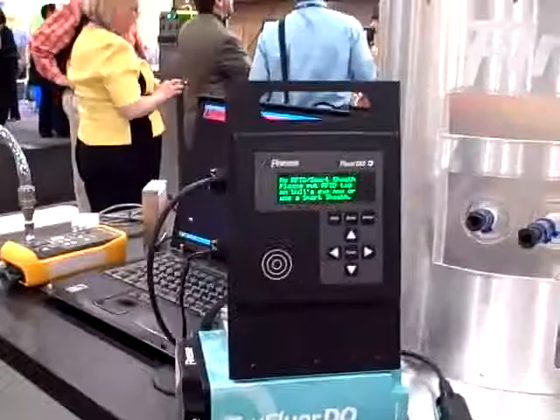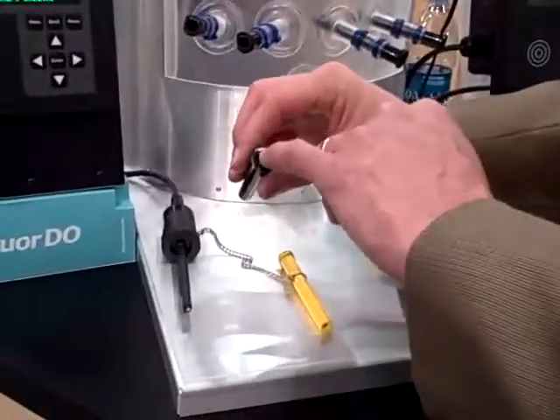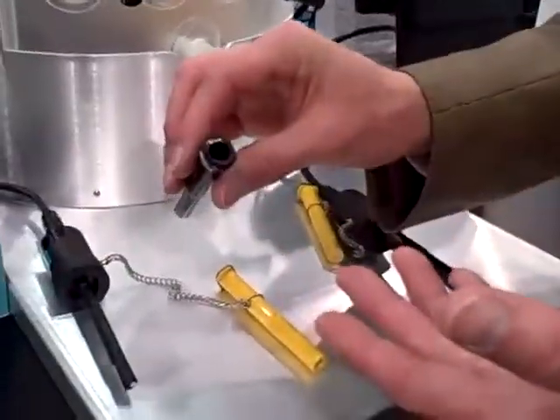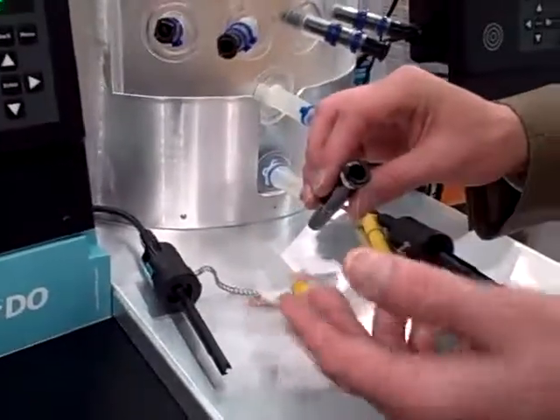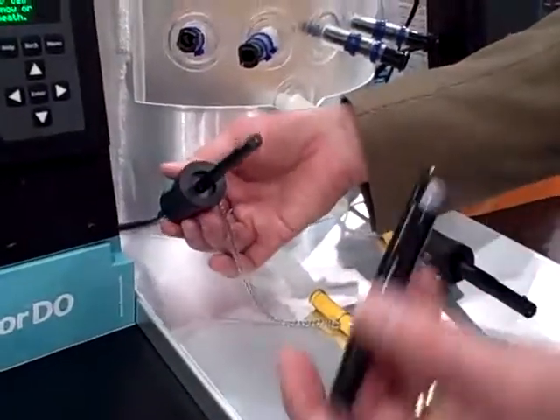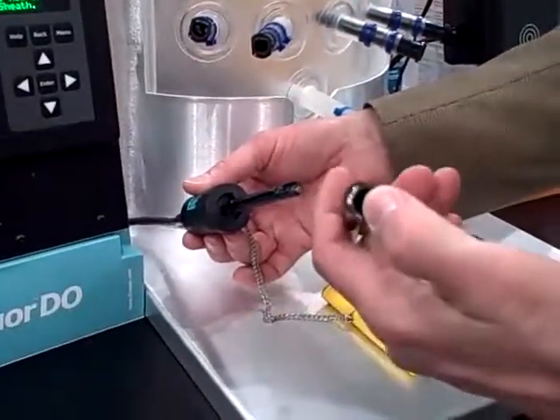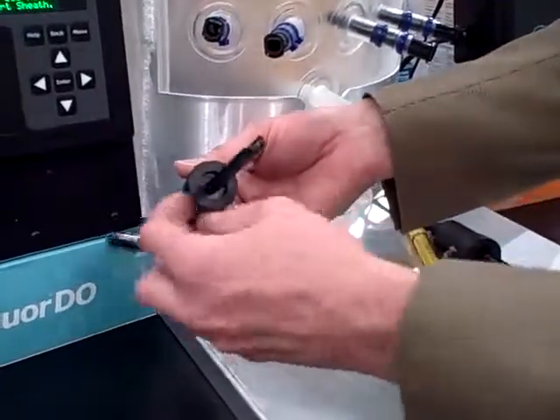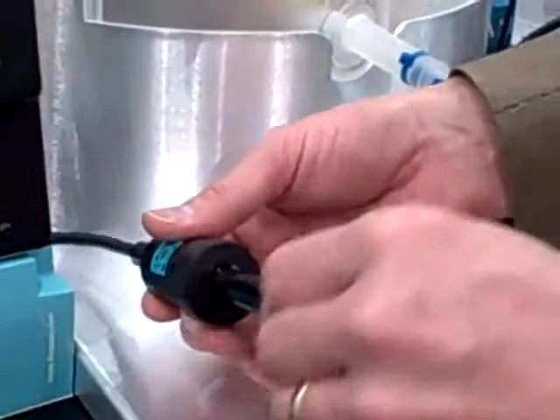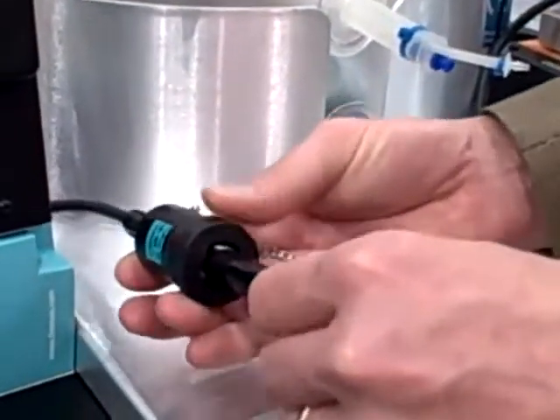The same thing is true for the DO. The DO sheath has the same features: pre-calibrated at the factory, calibrated with traceable gases, and it has the same chip in there and the same pins to read it. As you can see, it tells you it's not read. So slide it in, lock it, and it will read it automatically.